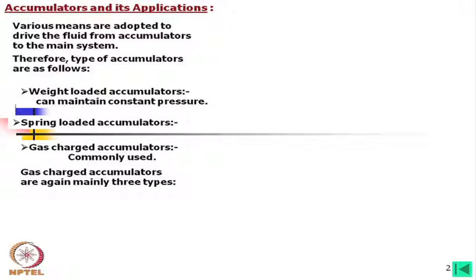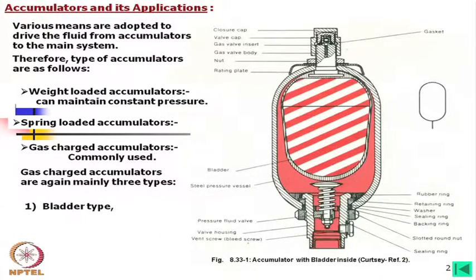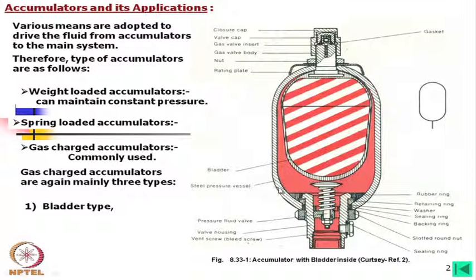Gas-charged accumulators are mainly of three types. The most common is the bladder type. If we study the figure, we find that the outside is the main casing — a steel pressure vessel — and inside there is a bladder which is usually charged with gas. Nitrogen is very common, however one can use ordinary air also.